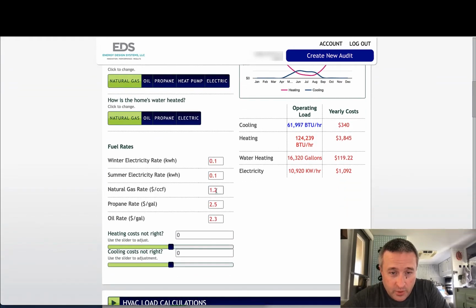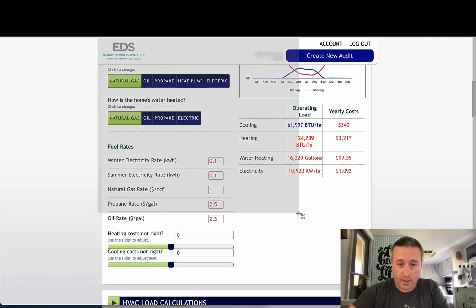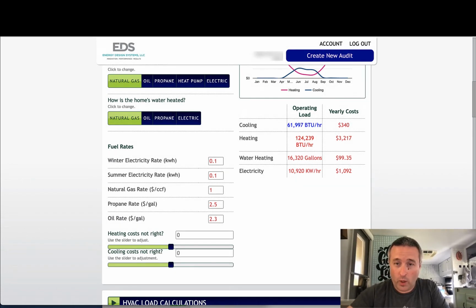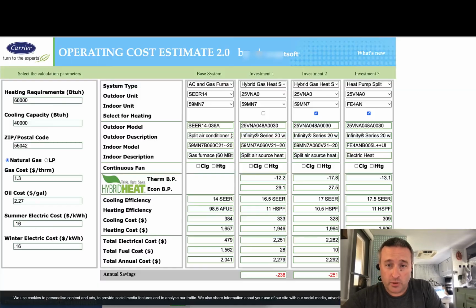Now let's see, natural gas, right. We're going to again start by simplifying this because we're going to true it up. And yeah, here we go: 62,000 cooling, 124 heating. From looking at the actual energy bills, we know it's way less than that, so it's half this and two-thirds of that. We can tell by annual costs that we're definitely not there, because heating cost should be around 1,900-ish, or heck, it's 1,650 here. Expensive electricity makes the math not as good.